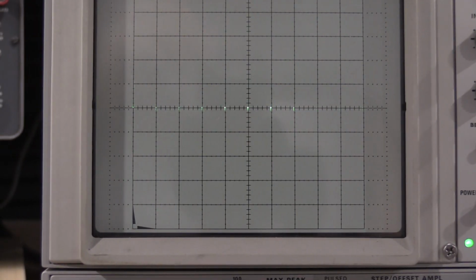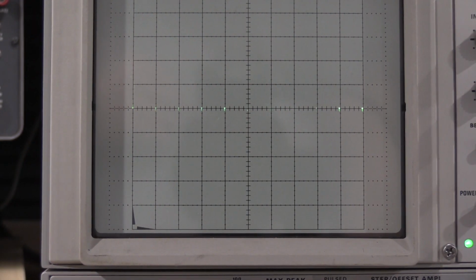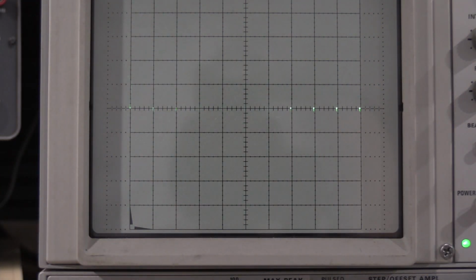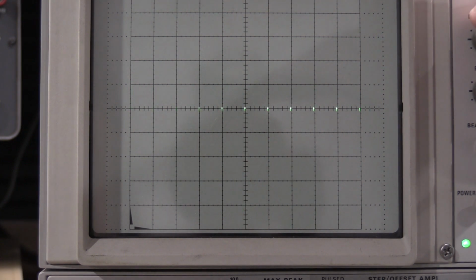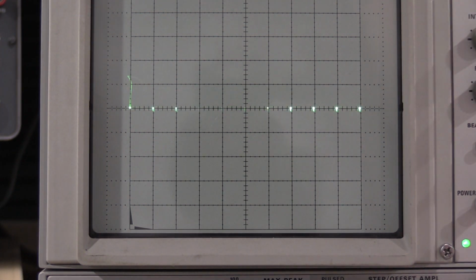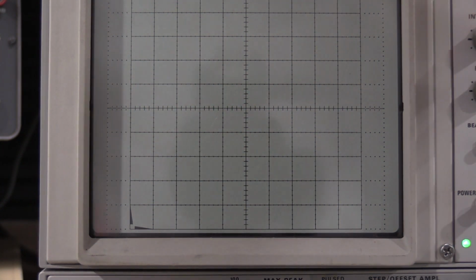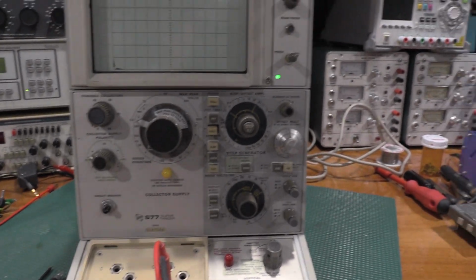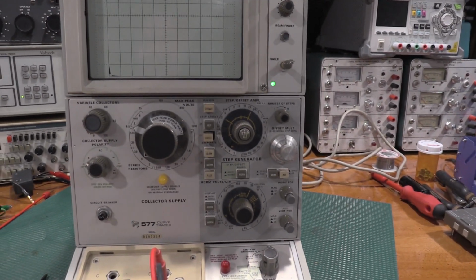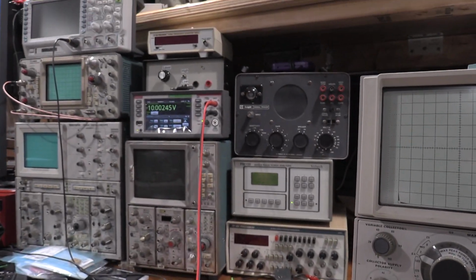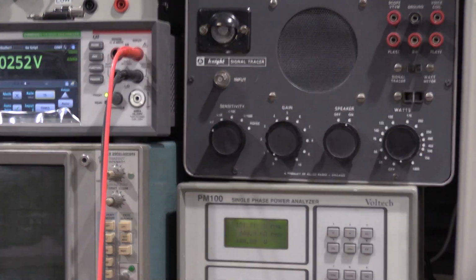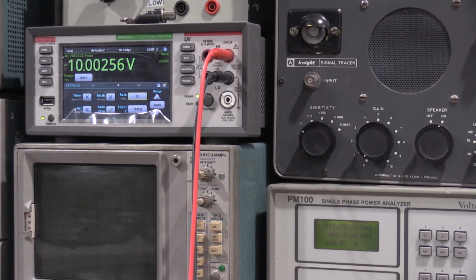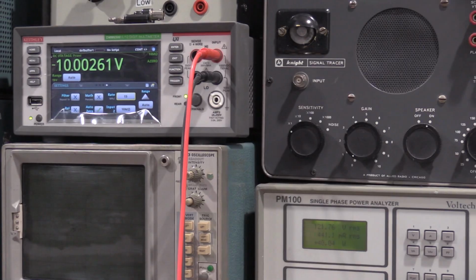Okay, for the step offset, we're supposed to have 1 spot per major division going across the tube. We do, 10 spots. That all looks very healthy. Everything looks good there, so I don't think that even needs to be adjusted, so we're going to leave that one alone. The next one was to test the offset multiplier. We have the offset multiplier set to 10. We needed a meter reading of 10 volts. We have a meter reading of 10 volts. So everything is good there.